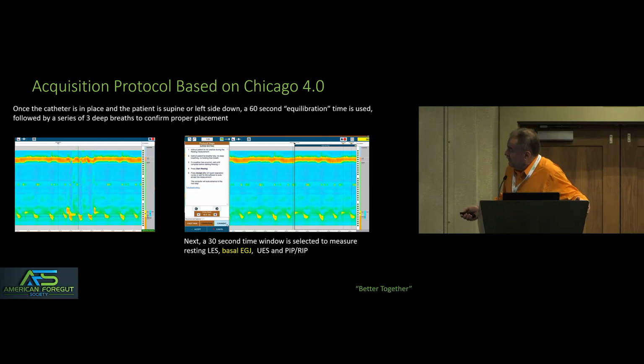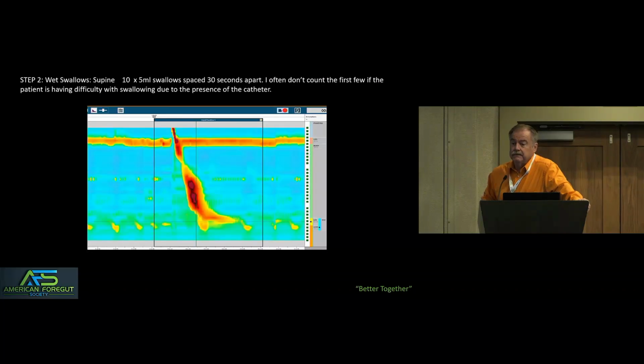With this technique, you'll have a 30-second time bar. It'll automatically close, at least in the Diversatek software. It automatically closes at 30 seconds. So easy peasy. Catheter's in, patient's comfortable. You've done your assessment, your catheter's placed correctly, and you've got resting pressure. That's just the beginning. The next part of the protocol involves wet swallows. You can use water or saline. I use normal saline. It does make a funny face on the patient, but I'm looking at impedance too, so I want to see a nice impedance clearance if I can.